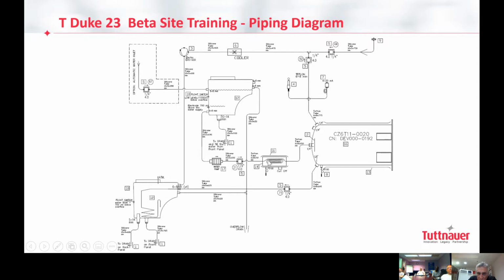This way, any bubble of water which comes into this coil and starts moving there, because don't forget we have vacuum inside the chamber, remember, we are now after the third pulse and we are deep down there, this bubble of water gets vaporized, gets converted to steam, and goes into the chamber. Another bubble, another pulse, and pulse, and pulse. This way we get the climbing up of the pressure and the temperature, of course. But for now, we are interested in the pressure because we are removing the air.